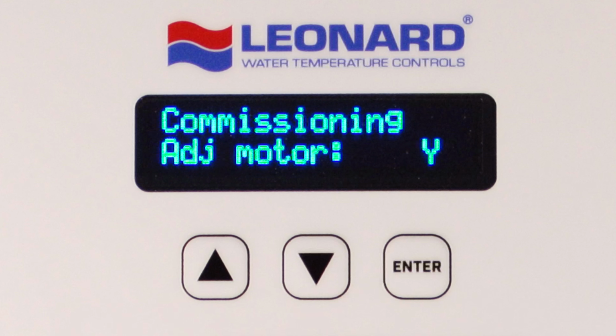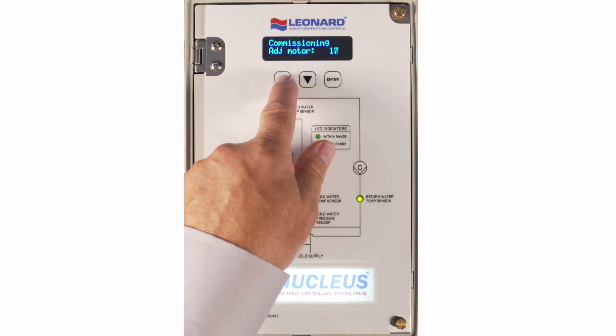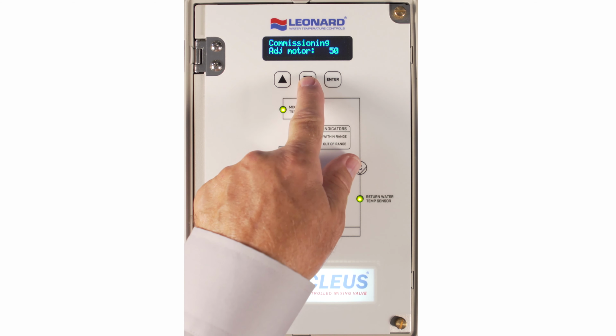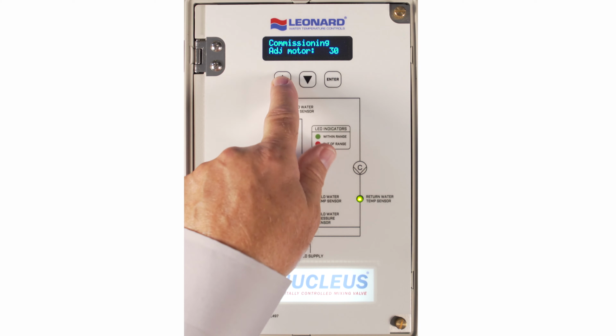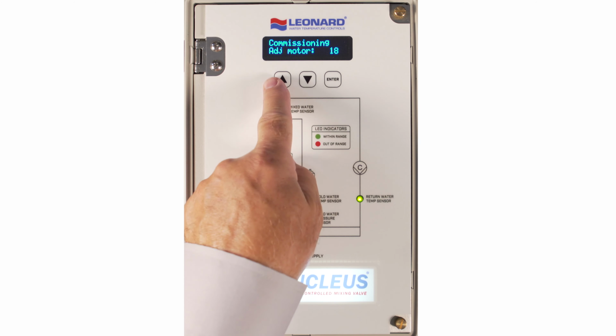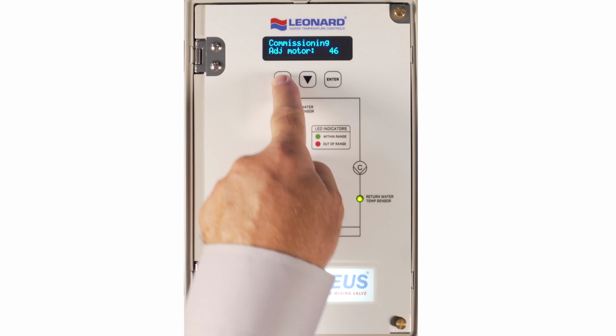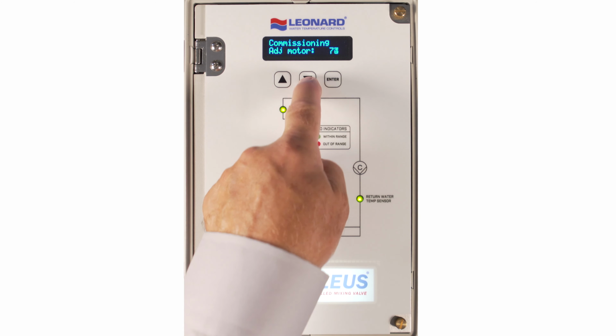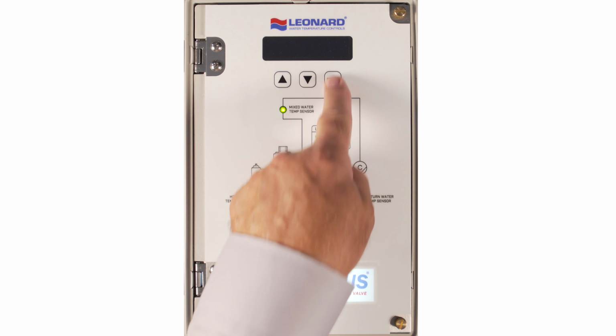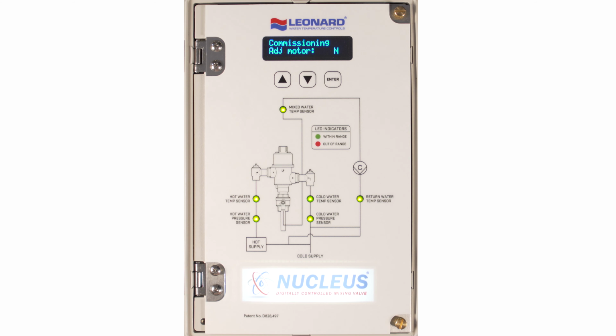When Y is selected, the motor position is only being controlled by the authorized user, and the screen will display the current position of the motor. Pressing up will move the shuttle to allow more hot water into the valve, while pressing down will move the shuttle to allow more cold water into the valve. To exit this mode, press the Enter key. Once this mode has been exited, the valve will revert back to its standard operation.